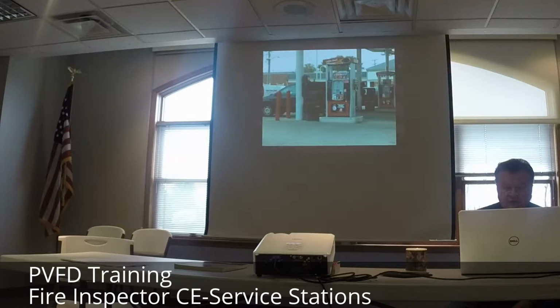Breakaways right there for this long arm. Those should all be attached. Like I say, the biggest thing I've noticed is that I'll go in and a pump and a half is taking forever to fill. It's because of the breakaways, where someone drives off with the nozzle in there. They say it takes about 200 pounds of pressure. I don't know what that means exactly. I just know that a car can pull it off, but I can't stand there and do it. That's about all I can tell you.